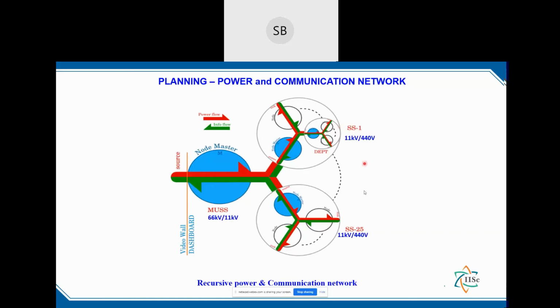From here, we distribute to a total of 25 substations, SS1 through SS25, which operate at 11 kV to 440 volts. These 25 substations feed the required departments, laboratories, residential quarters, and other areas. Each substation typically feeds around 4 to 5 or 6 departments depending upon the load. At the institute, we have more than 45 to 46 departments, utilities, hostels, and several other facilities, so the load is properly distributed using these substations.